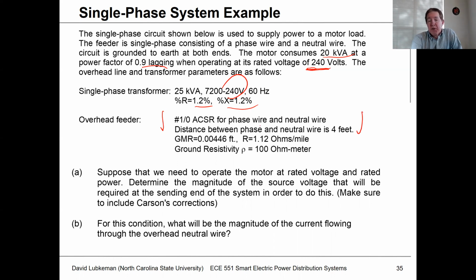GMR for that wire is 0.00446 feet, and the resistance is 1.12 ohms per mile. Ground resistivity is 100 ohm-meters, which we're going to use for the Carson's correction calculation. So again, what I want to do is work backwards and figure out the source voltage. And then the other thing I want to do is figure out how much of that current is flowing through the overhead neutral wire versus the earth return.